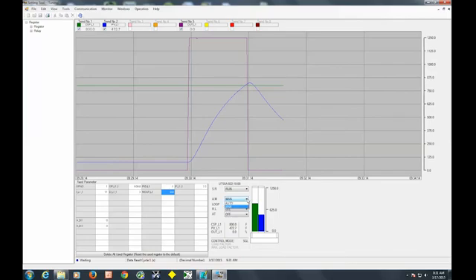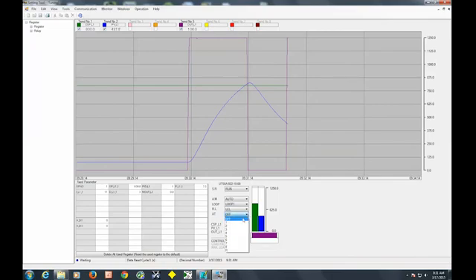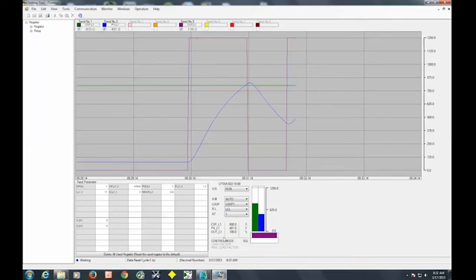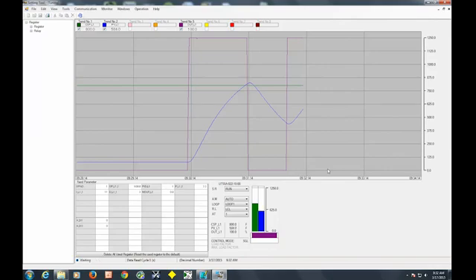I'm going to put it back in auto and then go down to AT and choose 1 for the first PID group. And what we're seeing here is the output went to 100. That's your purple line. The blue line is your temperature. It's coming up trying to get to set point. So this is the first of our three cycles that it's currently doing. And we're approaching the set point here.